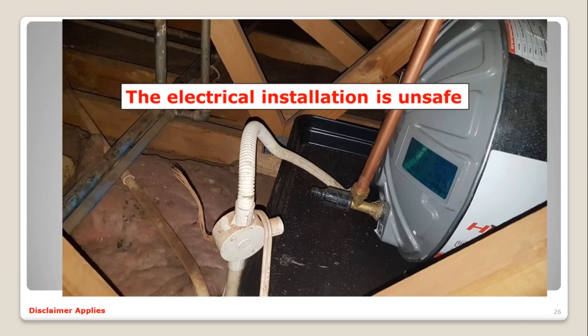In this particular installation, you will see that the earthing wire was just cut off. It was not secured back to the geyser flange. So this installation has no earthing, meaning that the circuit breaker, even on an overload current without a dead short, will just keep on overloading until it gets to a certain point where the circuit breaker will overheat and trip. And again, no earth leakage. If this system was connected to earth leakage, there won't be any earth detection on this. So it's very important to make sure that the earth wire is connected to the geyser and bonded to the hot and cold water piping. Next slide, Emma.